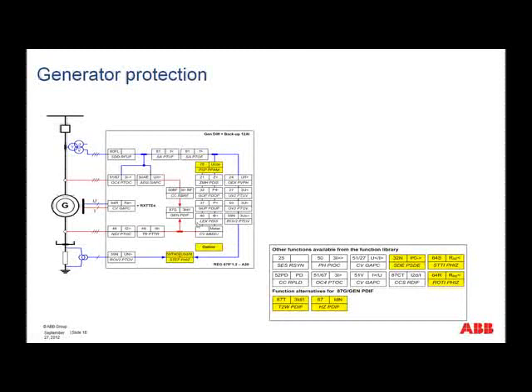And then there are also other functions that we would want to include for the metering or more measurements, I guess you could say. And there we'd be looking at measurement for display purposes of current, voltage, megawatts, megavars, etc. Then, of course, there may be other functions that would be required, maybe instantaneous overcurrent, maybe pole discrepancy, maybe voltage dependent overcurrent. And together, all of these functions would then make up your overall protection scheme to protect the generator.